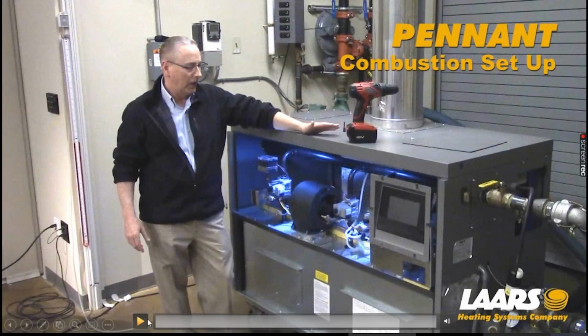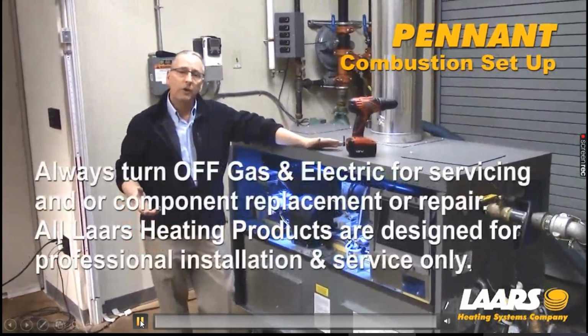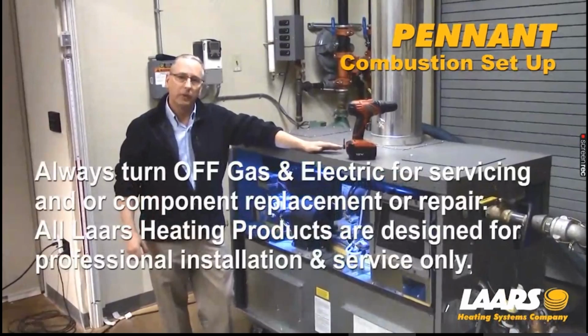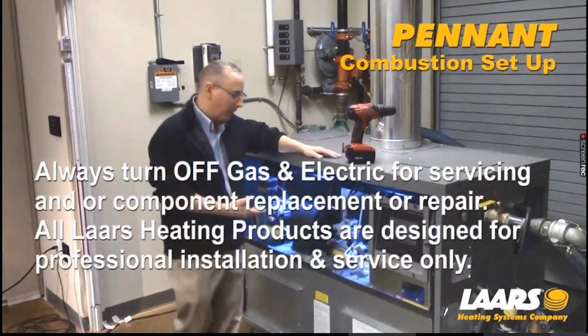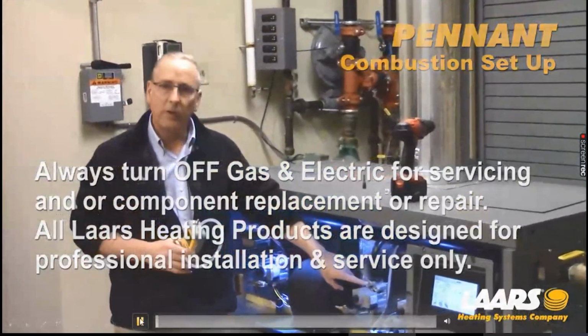I'm going to just go ahead and play the video. As you can see, I've removed the cover. Prior to doing that, I shut off gas and electric. Our next step is check the incoming gas pressure. We need the gas off, and I'll remove one of the test plugs. What I forgot to mention was I'm showing the Pennant combustion setup.